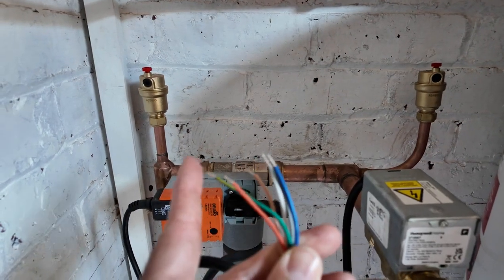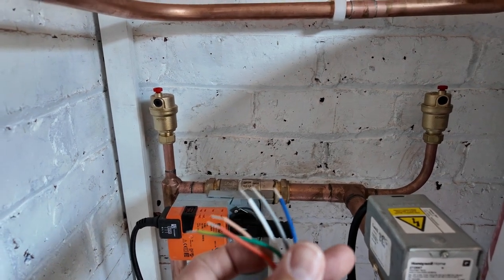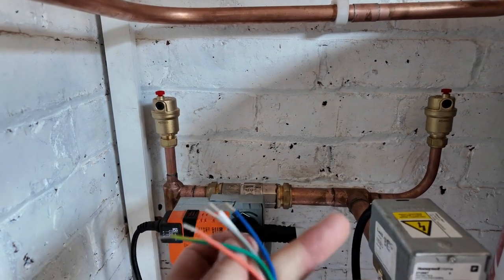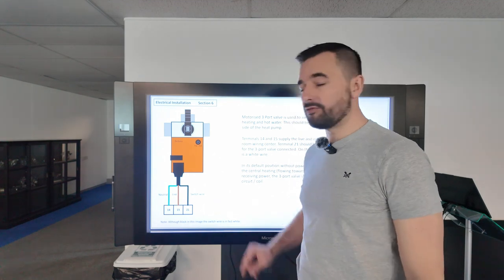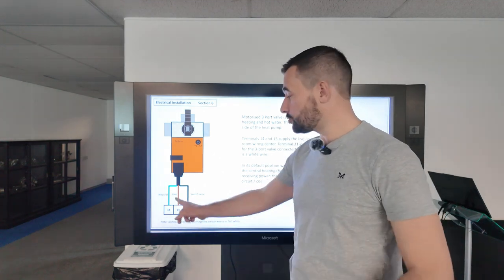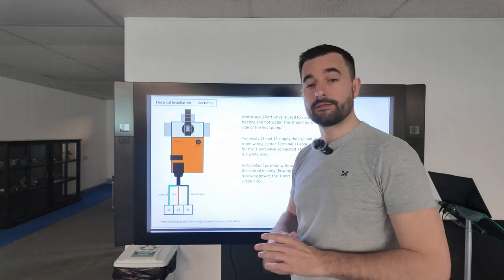The Honeywell valve has earth, neutral being blue, and the grey and orange are unused — the brown is fed from the high limit stat. The Belimo 3-port valve only has three connections: it has a permanent live, neutral, and a switch wire which is either black or white.